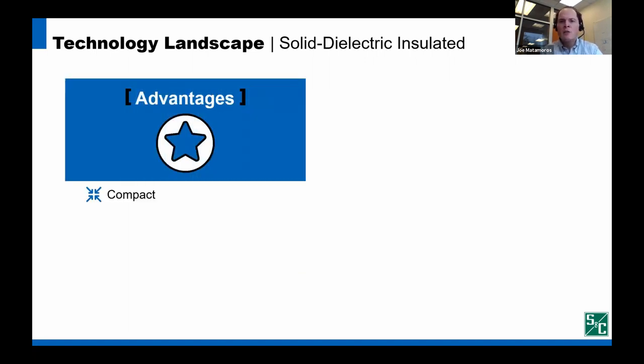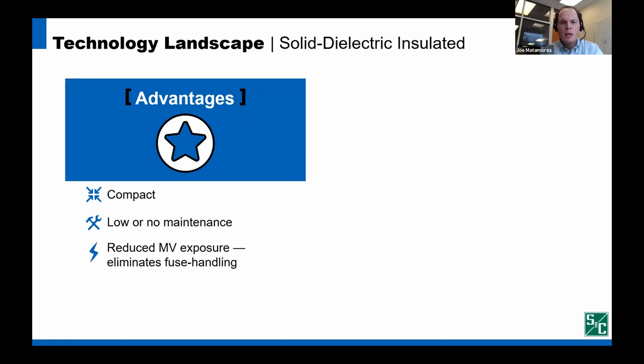The advantages of solid dielectric gear are very similar to gas insulated or oil insulated gear. Like gas insulation, solid dielectric allows a more compact insulation than air insulated gear. Since everything is molded and sealed, there's low or no maintenance required, as with gas insulated gear. There are no fuses to handle. The gear is submersible. And all of the advantages so far are the same as gas insulated gear, where solid dielectric has a differential advantage that does not use oil or SF6.